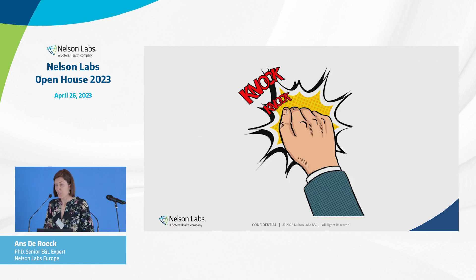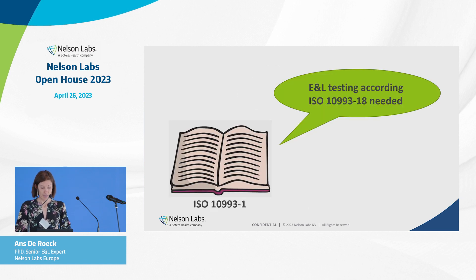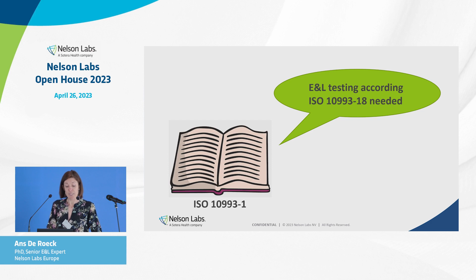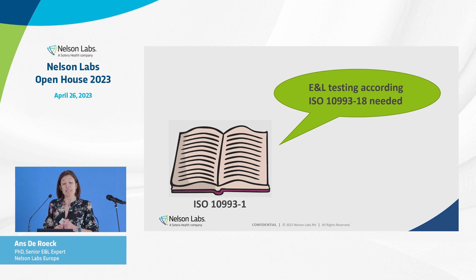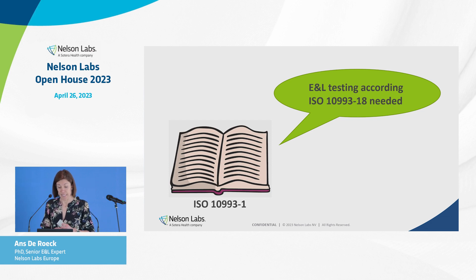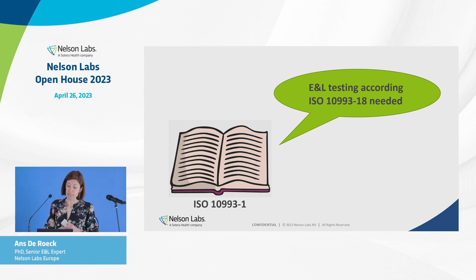So when do people knock on our door? As just explained, according to ISO 10993 Part 1 you have to write a biological evaluation plan, and in this plan it can be mentioned that E&L testing according to ISO 10993-18 is needed — very likely to address biological endpoints like carcinogenicity, genotoxicity, and systemic toxicity without the use of animals.